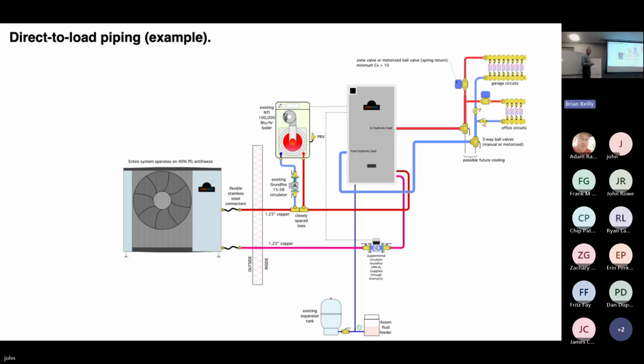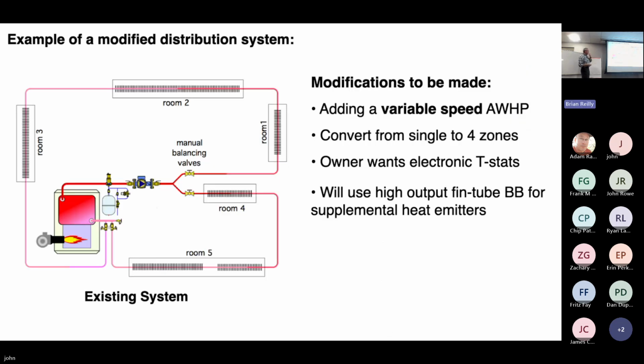You could come up with other scenarios. For example, you could enable the heat pump to operate if it's below 50 degrees outside. Or you could have a master thermostat somewhere in the house. When it calls for heat, it enables the whole system to operate, and the thermostatic valves just act like trim controls on that. But anyway, that's a direct to load scenario.